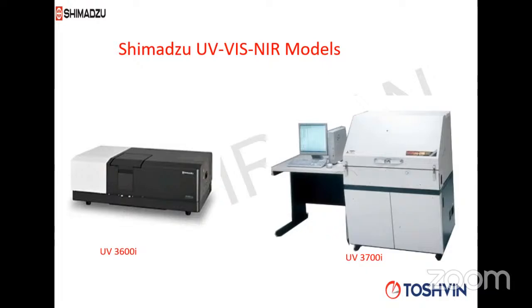I told you, normally we cannot go below 190 nanometer because most of the equipments start from 190 nanometer, but this particular equipment can go much below that. And that area is known as the vacuum UV region. So UV 3700 is a very, very expensive model, purely a research model. It can even work in the vacuum UV region. So these are the two important UV visible NIR models from Shimadzu.